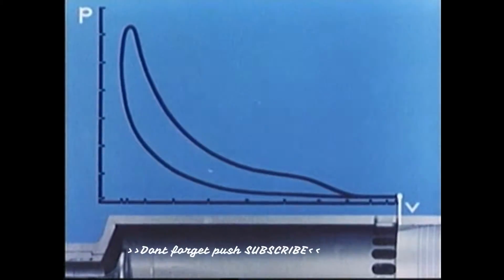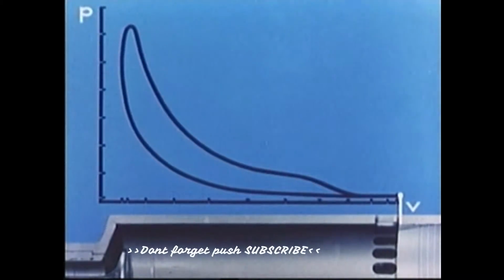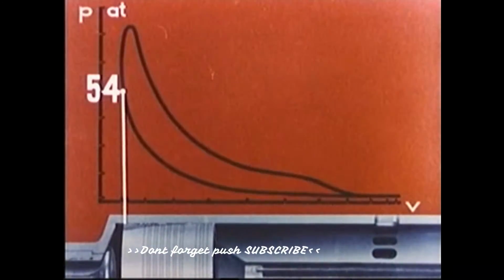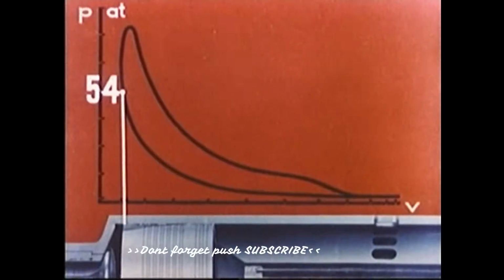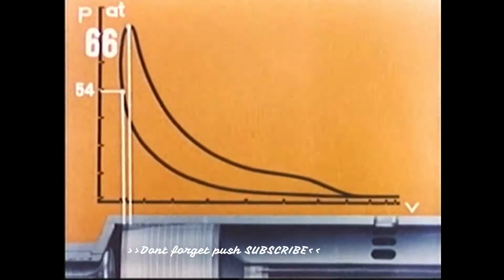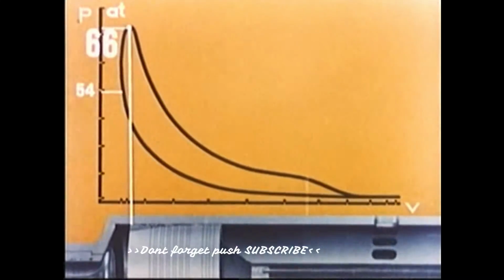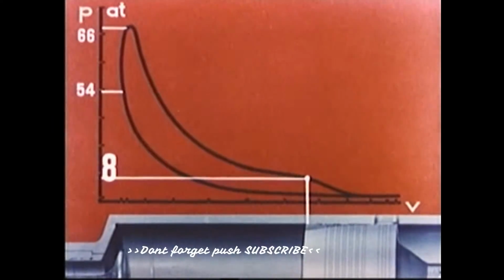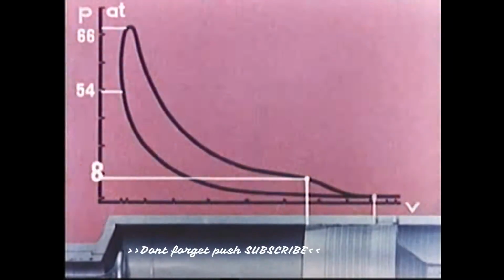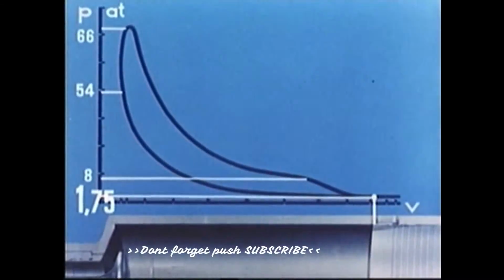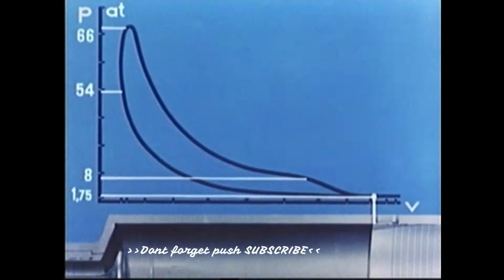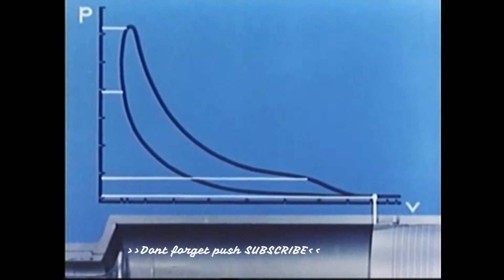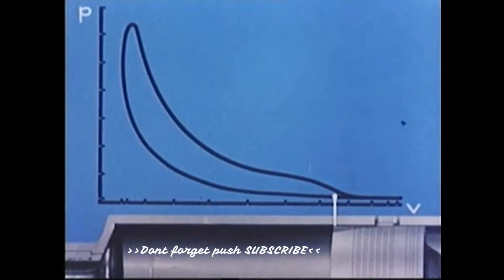The characteristic pressures are approximately a compression pressure of 54 kilograms per square centimeter, maximum pressure 66, exhaust pressure 8, and scavenger air pressure 1.75 kilograms per square centimeter. From the indicator diagram, the indicated output may now be computed.